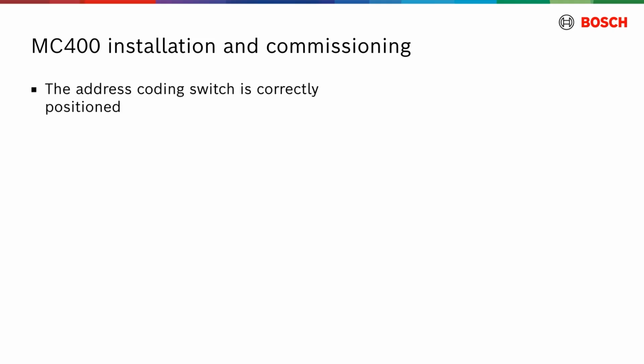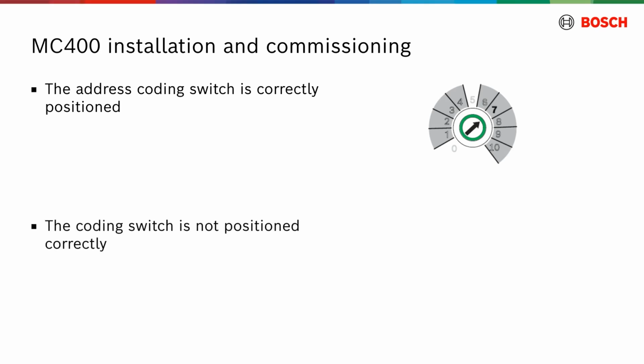When the address coding switch is correctly positioned and communication through the bus system is successfully established, the operating indicator lights up green continuously. If the coding switch is not positioned correctly, the operating indicator initially does not light up and then turns red. For comprehensive guidance on assembly, electrical connections, and commissioning, please refer to the MC400 module installation manual.